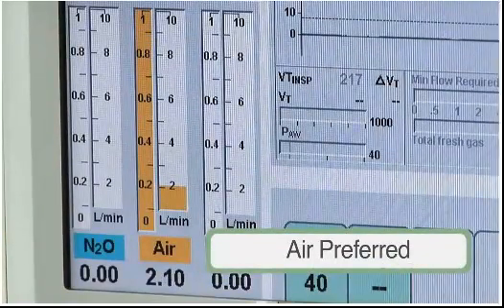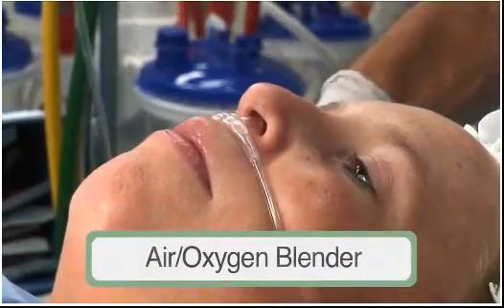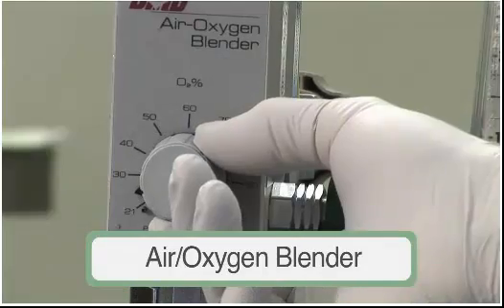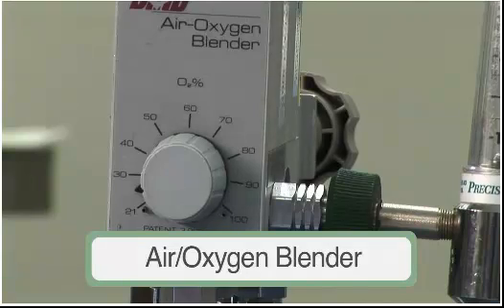There is no risk of a flash fire if the oxygen concentration is less than 30%, but many items that do not burn in air will burn in 30% oxygen. Three options are recommended for blending oxygen with air during exceptional surgical cases where open oxygen delivery is essential. The most reliable approach is to use an air-oxygen blender to provide gas to the nasal cannula or mask — the oxygen concentration is selected directly and these devices are accurate. However, air-oxygen blenders may not yet be present in many anesthetizing locations.